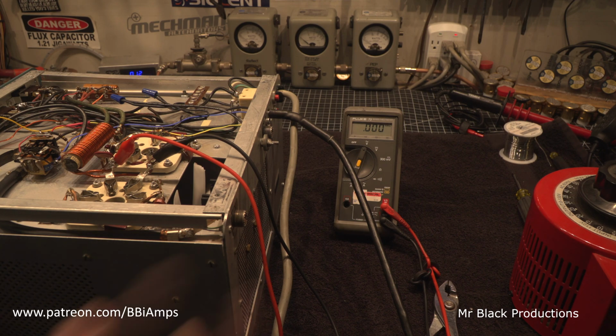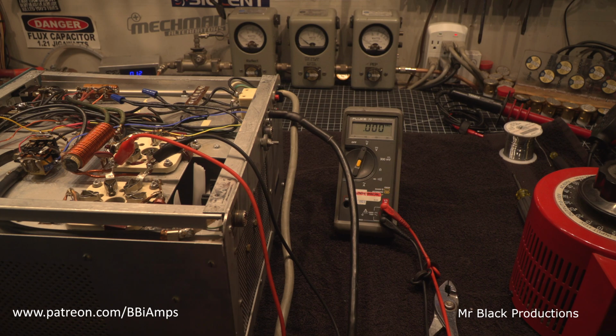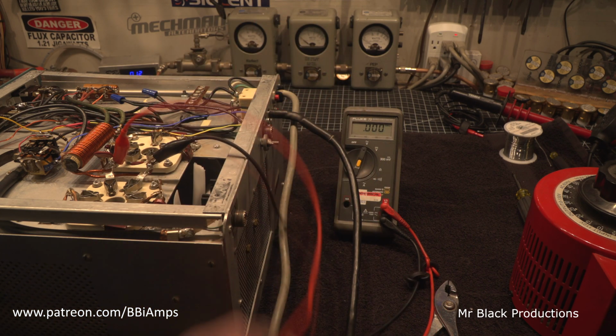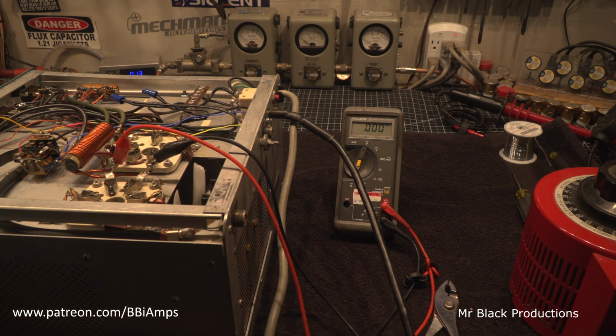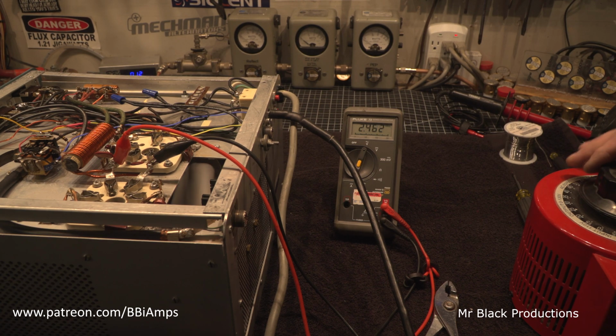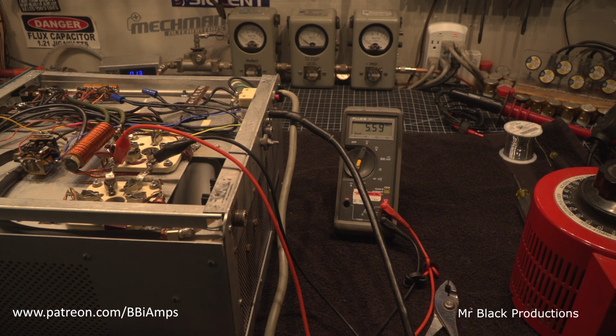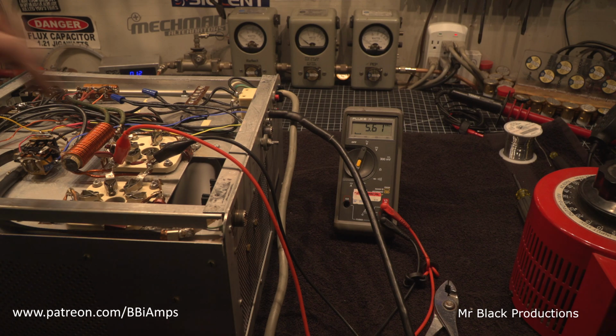So right now, we've got our probe set on AC. Your tube works on 2 separate principles: AC for the filament, but DC voltage for the bias. So let's go ahead and bring our filament on. So we brought the amp on, and for the 3-500Z, you're looking at roughly about 5 volts, 5.5 volts in the filament. So we're going to look at that on AC, on this lead and the other lead.